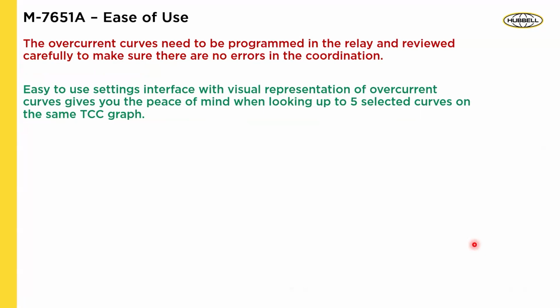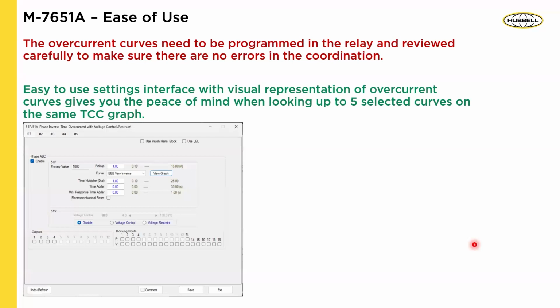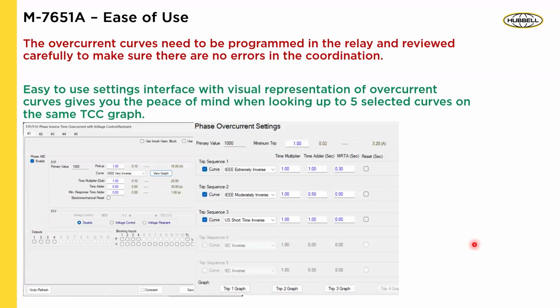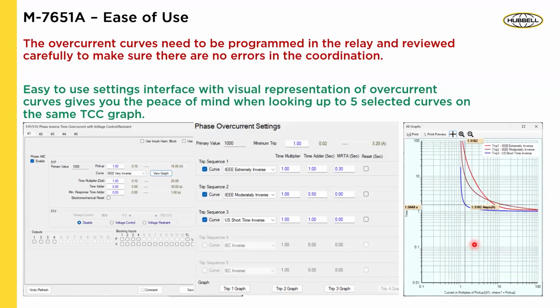Okay, the overcurrent curves need to be programmed in the relay and reviewed carefully to make sure there are no errors in coordination. So what we've done is we've given you visual cues, right? So we say, okay, you program it there. Now you have an overcurrent settings screen where you can choose which curves you want, what settings you want, and now you could see it on a screen. You could see all three curves right there. And then there's a cursor. You point on the cursor, it'll tell you exactly, if there's a fault of, let's say, two per unit, what does that look like in terms of operating time?